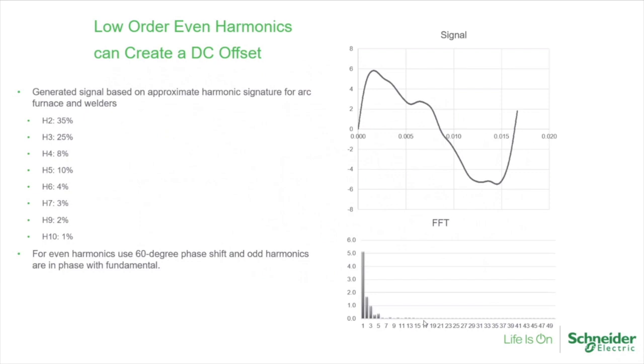And then this is an example of low order even harmonics and how they can create a DC offset on your system, or inject a DC voltage on your system. It's usually caused when you have asymmetry between the top and bottom half of your waveform. For this one, I used the following harmonics at the different percentages. I pulled these values from the typical harmonics generated by an arc furnace or an arc welder. They may not be consistent over one cycle and definitely not over time, but using the generator I have to create waveforms, this was just per one cycle.